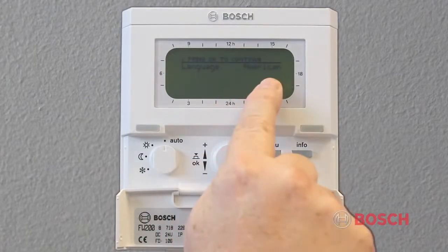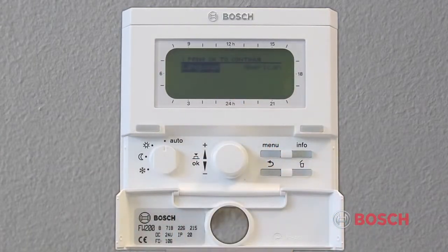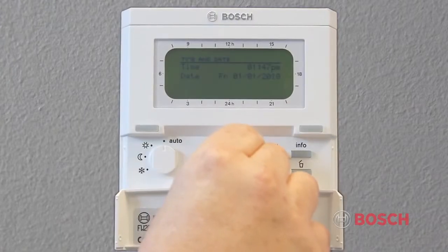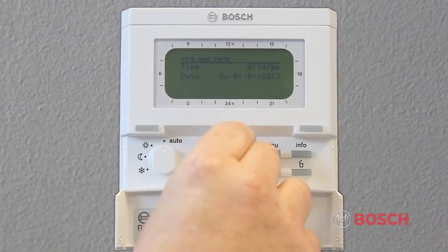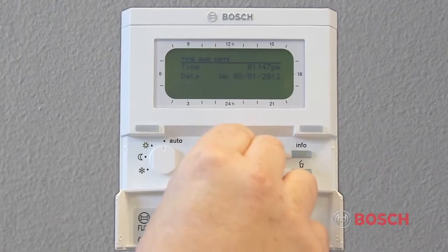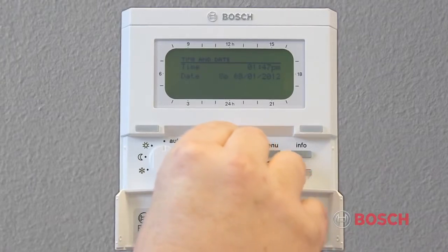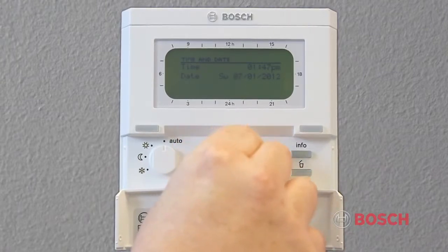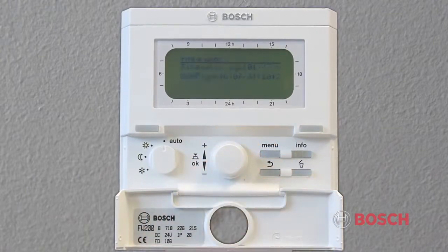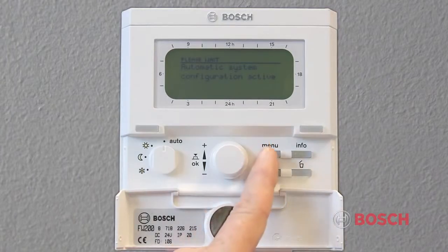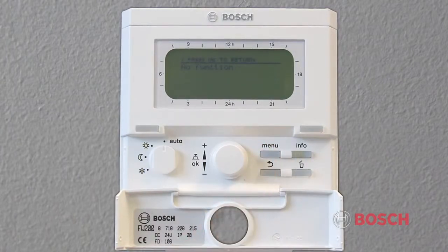When commissioning the FW200 for the first time, you must select the display language. Turn the selector up or down to select the language and then press to confirm. The FW200 will request you to set the date and time upon initial startup. To do this, turn the dial to adjust the time and date, and then press the dial to finalize your selection. You'll be asked about system configuration, which is only necessary if you have added controls. If you see this prompt, press and hold the menu button until it disappears.